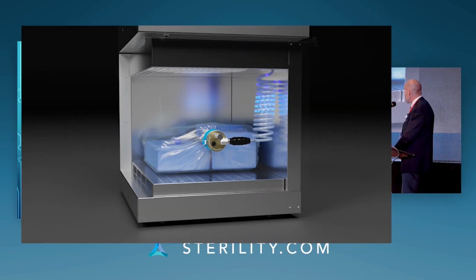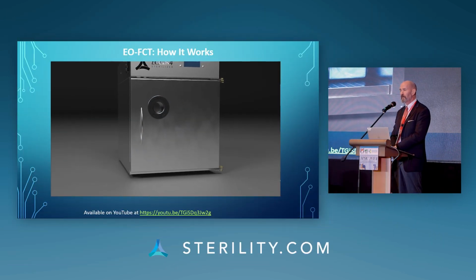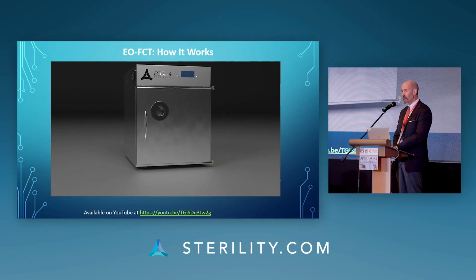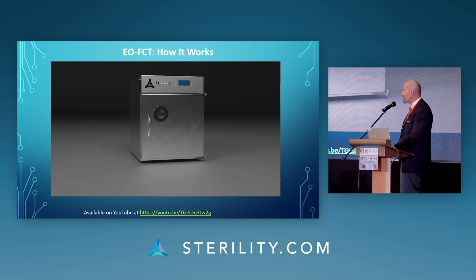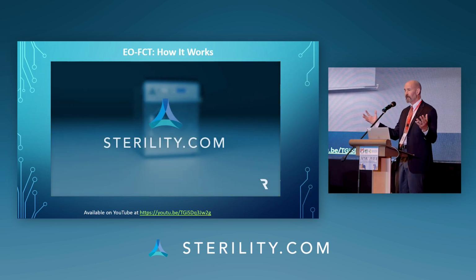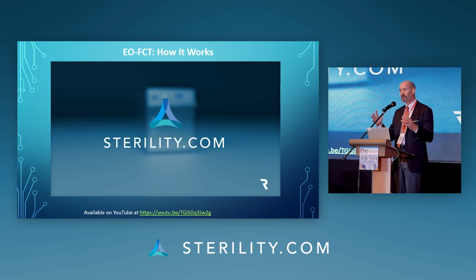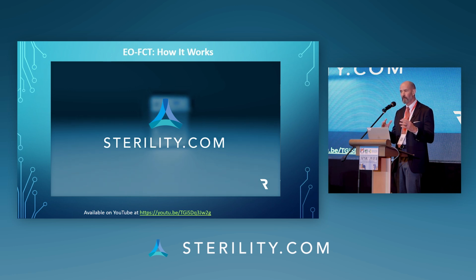It's a very significant improvement over traditional ethylene oxide because of that ability to reduce the size of the chamber to the size of the load that you're sterilizing, so there is no dead space. That's really the key to this process.